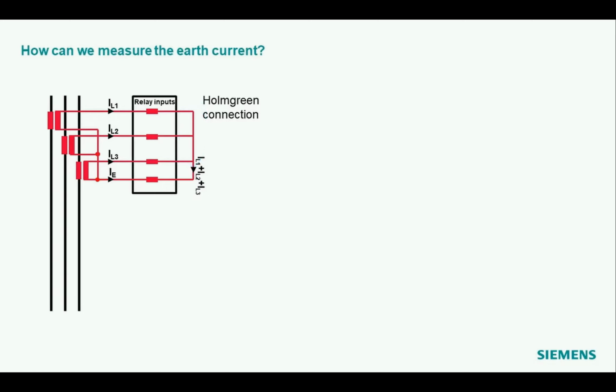Because you bring these 3 wires together, there you have a location where you have the sum of the 3 currents. And we normally connect this sum of the 3 currents to a 4th measuring input. This connection is called Holmgreen connection of a protection relay, and I would say that is a standard connection of a protection device.